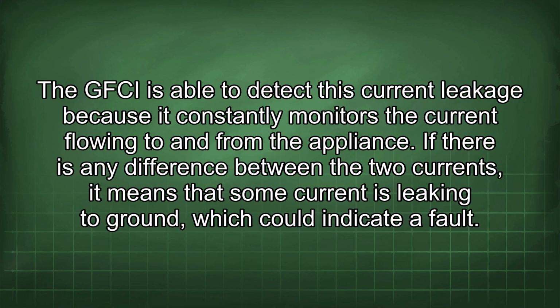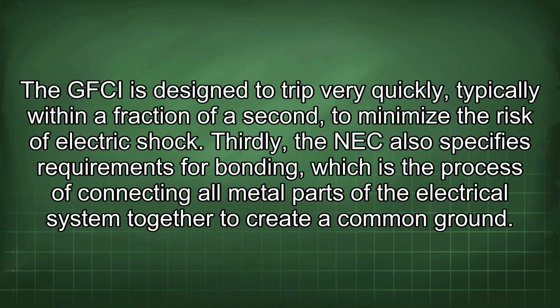The GFCI is able to detect this current leakage because it constantly monitors the current flowing to and from the appliance. If there is any difference between the two currents, it means that some current is leaking to ground, which could indicate a fault. The GFCI is designed to trip very quickly, typically within a fraction of a second, to minimize the risk of electric shock.